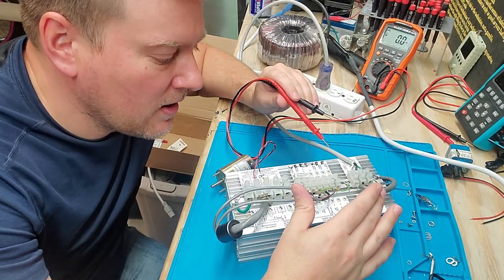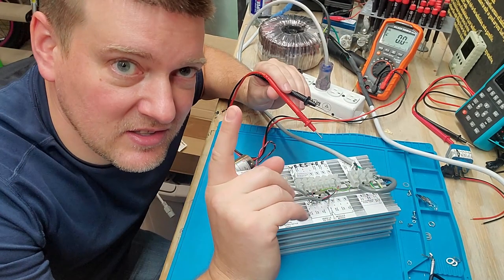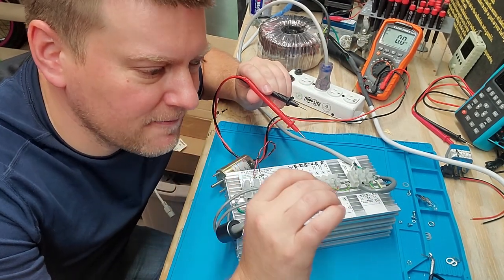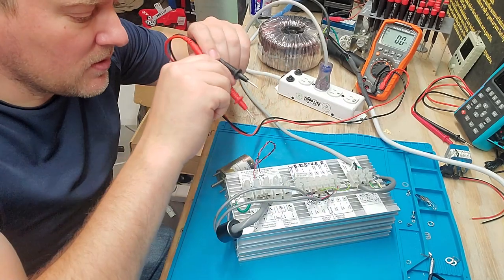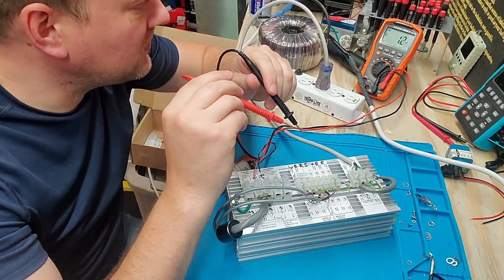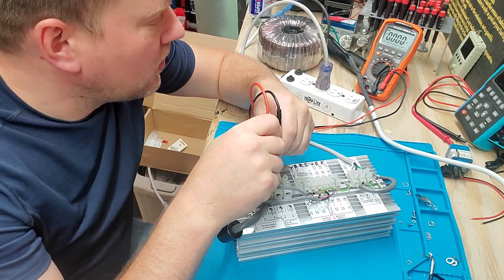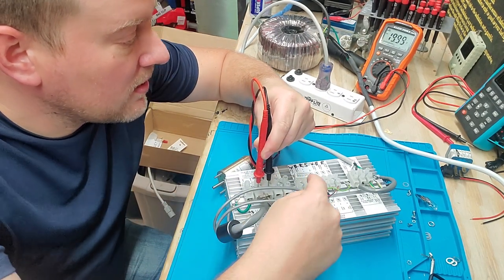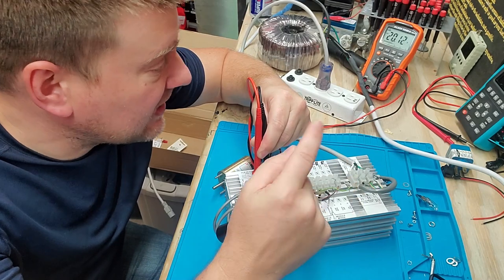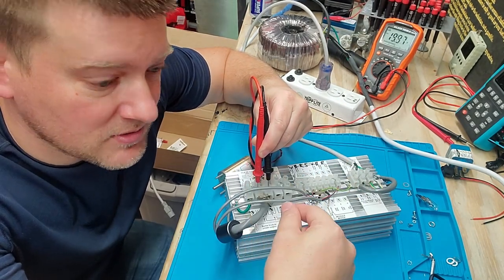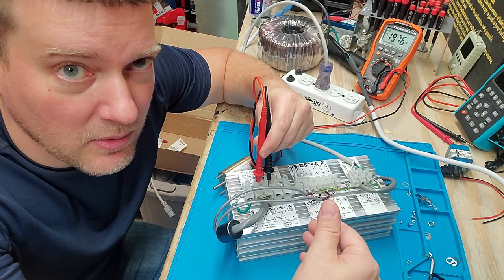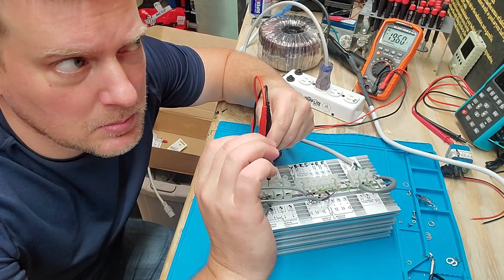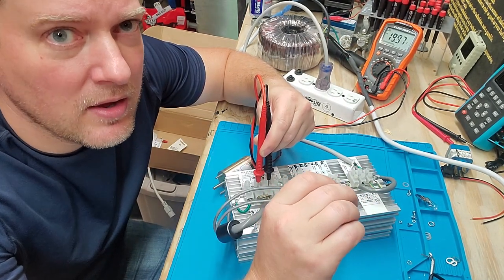So we changed out this guy here because I saw a weird extremely high voltage where there shouldn't have been. So over here on my output, I'm on DC, with the old potentiometer connected I was sitting at 53 volts. Now this is only a 24 volt power supply and I was sitting at 53 volts, which is absurdly high.